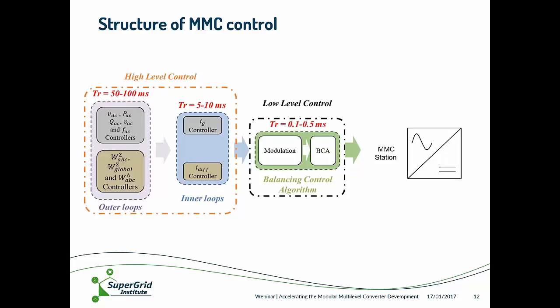The development of control strategy for the MTDC grid starts with developing a good control of the MMC itself. Here we see one possible architecture of an MMC control, consisting of cascaded control loops. The high-level control receives references of DC voltage, active or reactive AC power, etc.